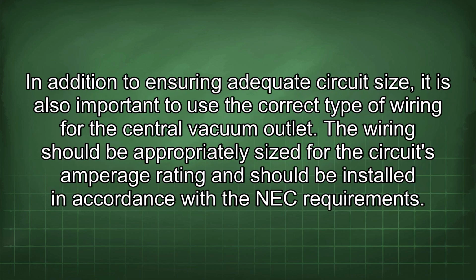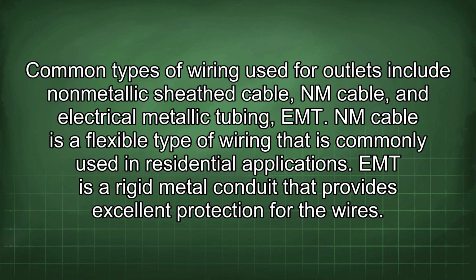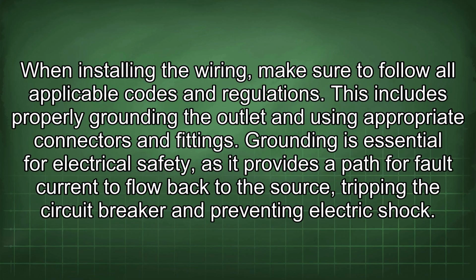In addition to ensuring adequate circuit size, it is also important to use the correct type of wiring for the central vacuum outlet. The wiring should be appropriately sized for the circuit's amperage rating and should be installed in accordance with the NEC requirements. Common types of wiring used for outlets include non-metallic sheath cable, NM cable, and electrical metallic tubing, EMT. NM cable is a flexible type of wiring that is commonly used in residential applications. EMT is a rigid metal conduit that provides excellent protection for the wires. When installing the wiring, make sure to follow all applicable codes and regulations. This includes properly grounding the outlet and using appropriate connectors and fittings.